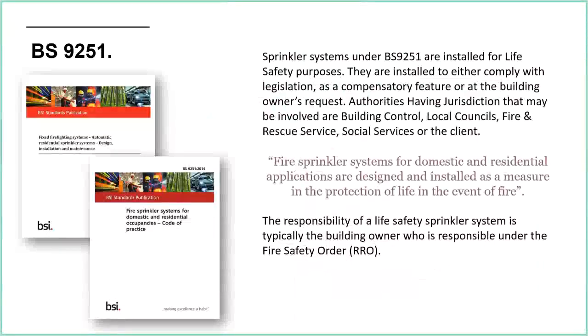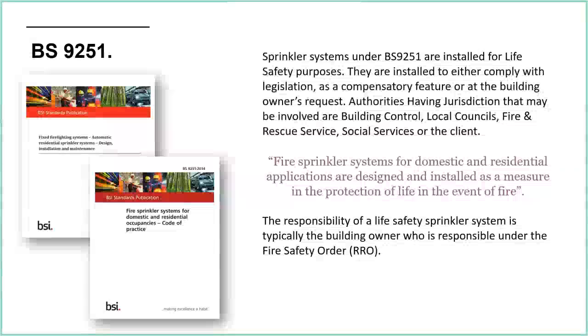Under BS9251, it makes it very clear that these sprinklers are for life safety purposes — you shouldn't be installing 9251 for property protection. There may be various authorities having jurisdiction: building control, local councils, fire and rescue service, social services, and the client themselves. The responsibility generally sits on the building owner under the fire safety order — the RRO — in terms of looking after all fixed fire suppression equipment.